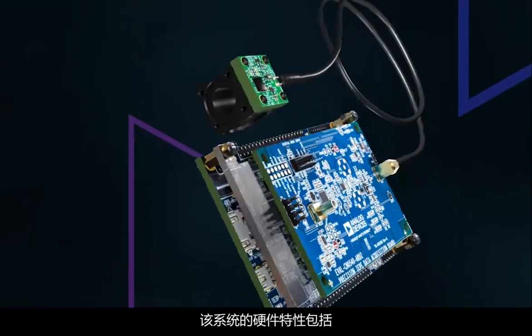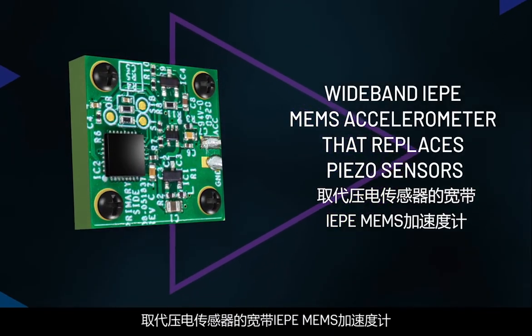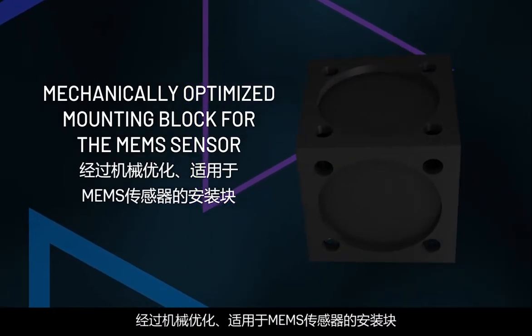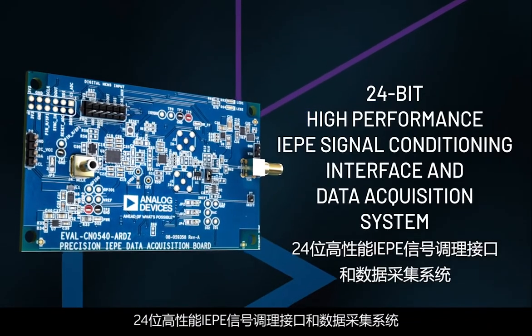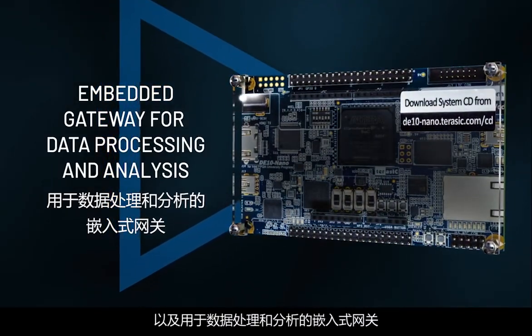The hardware features of the system include a wideband IEPE MEMS accelerometer that replaces piezo sensors, a mechanically optimized mounting block for the MEMS sensor, a 24-bit high-performance IEPE signal conditioning interface and data acquisition system, and an embedded gateway for data processing and analysis.